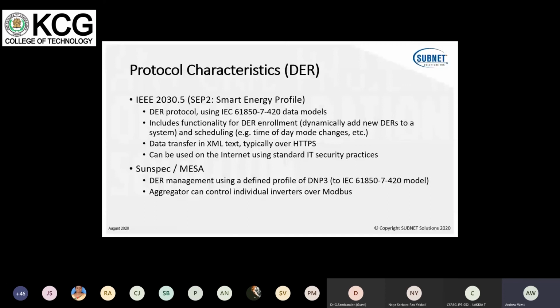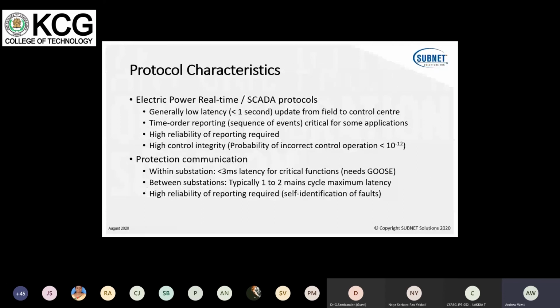So typical characteristics: electric power and real-time SCADA protocols have a low latency. They report data in event time sequence for critical applications. They've got a high reliability for reporting and a very high control integrity, so the chance of an incorrect control operation is very low.